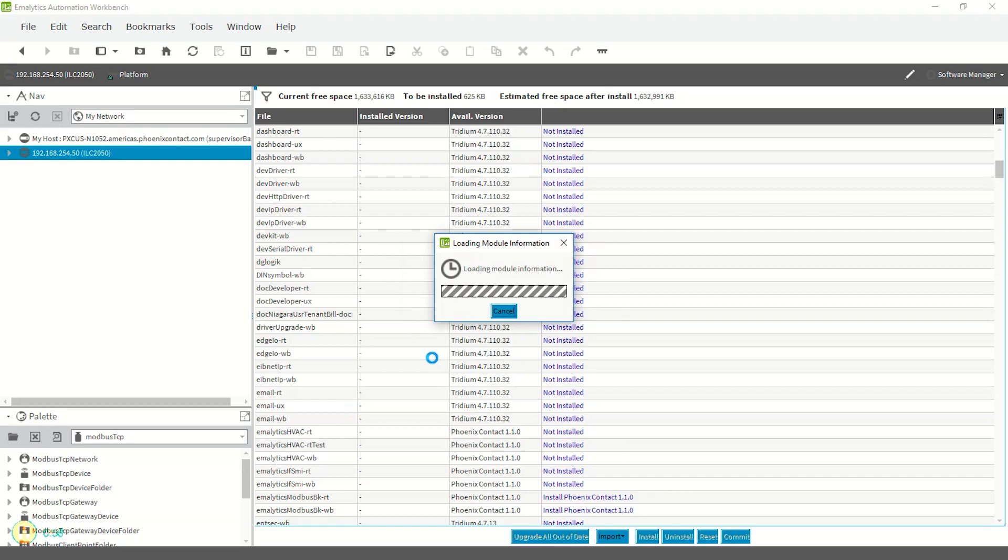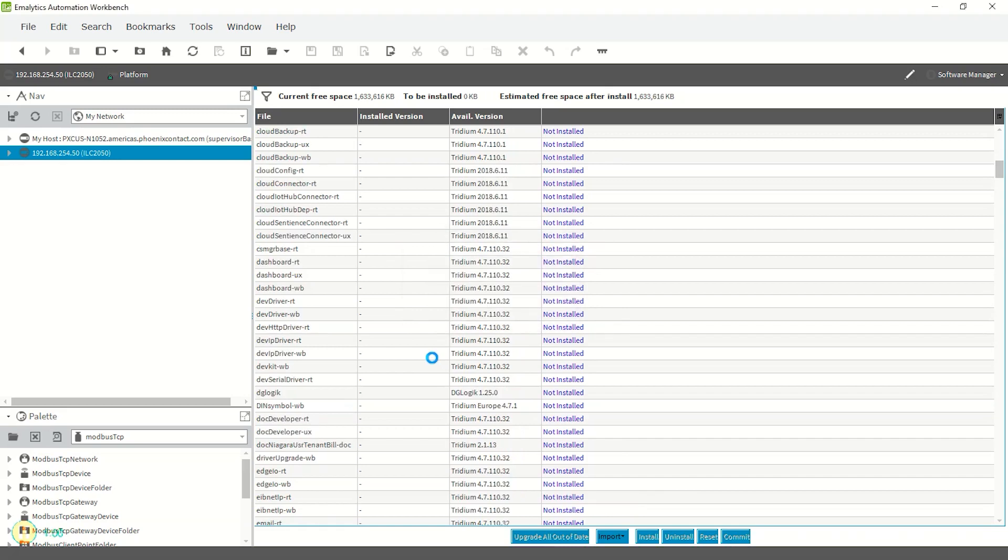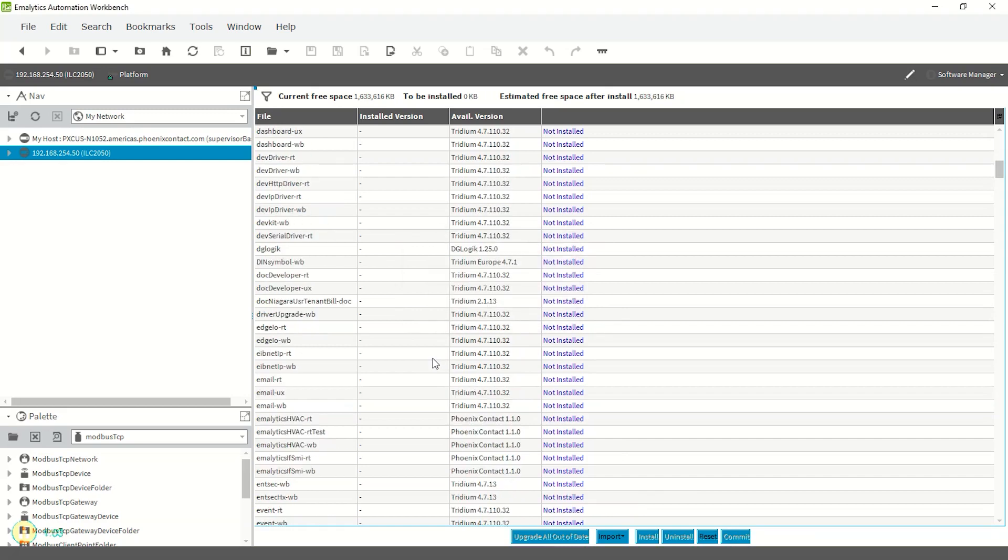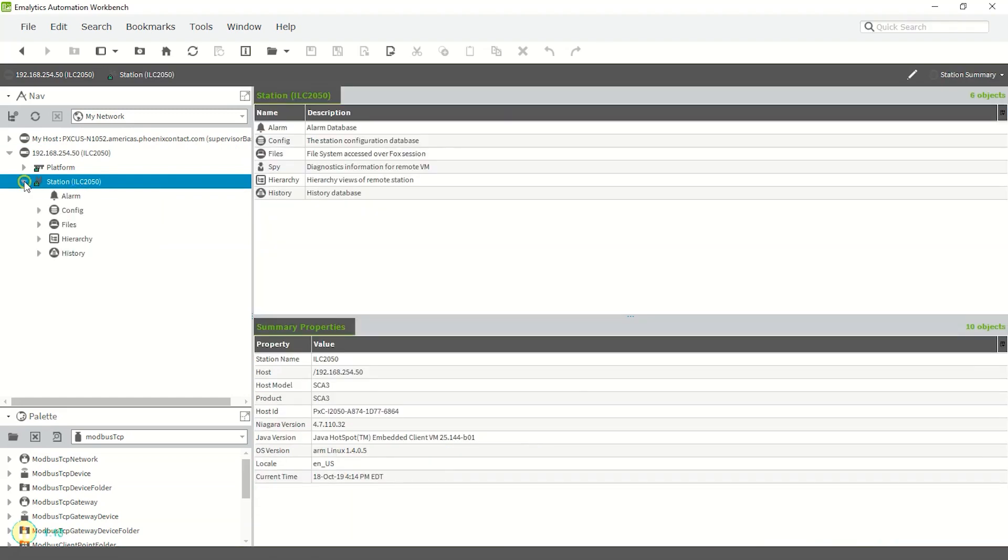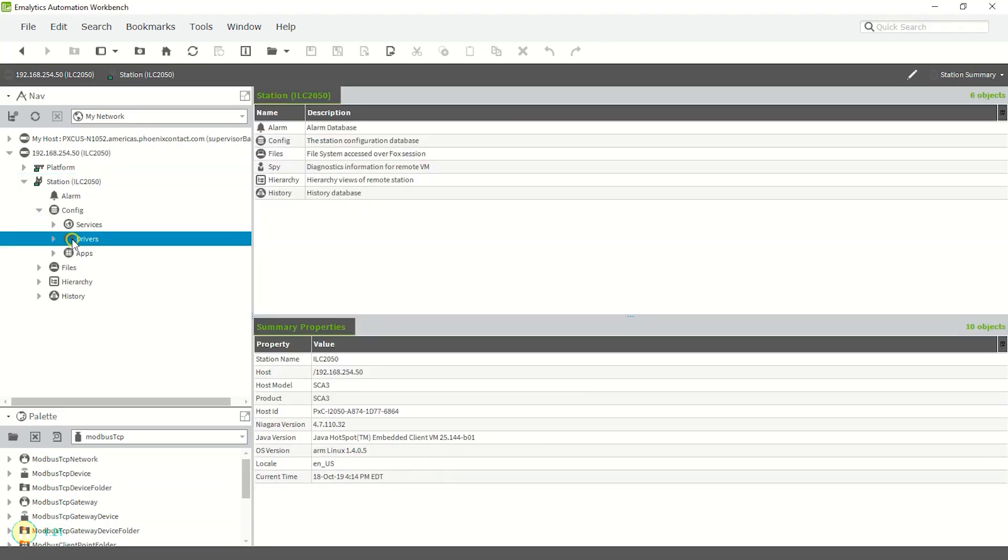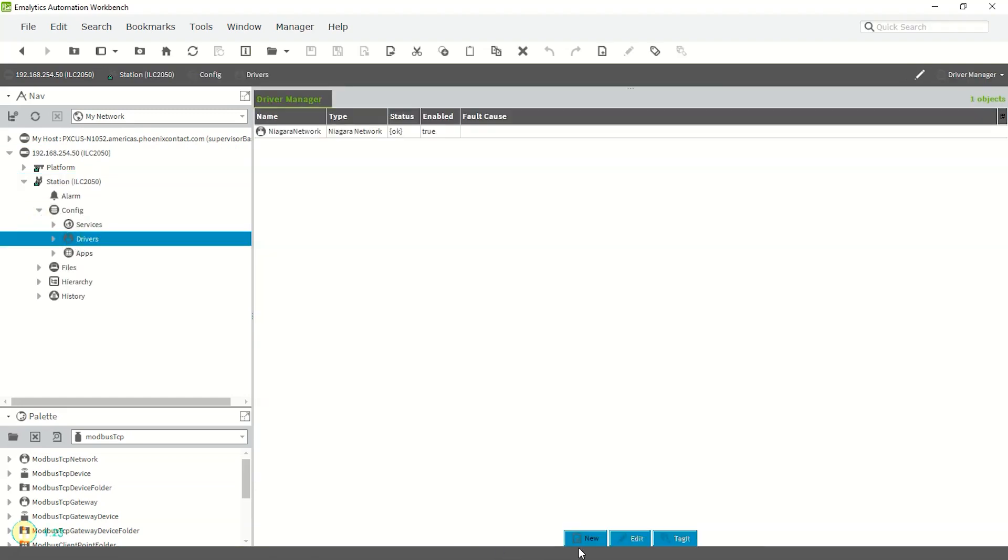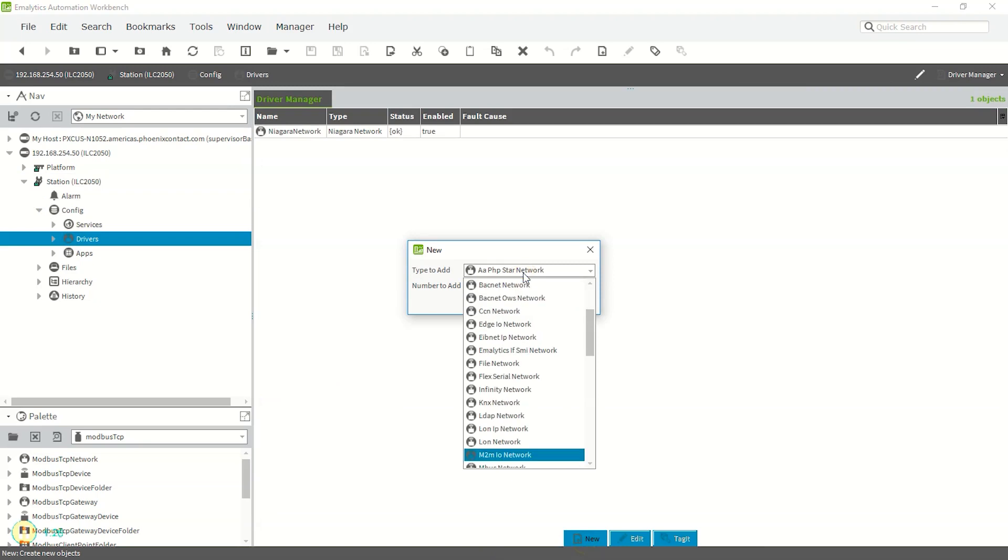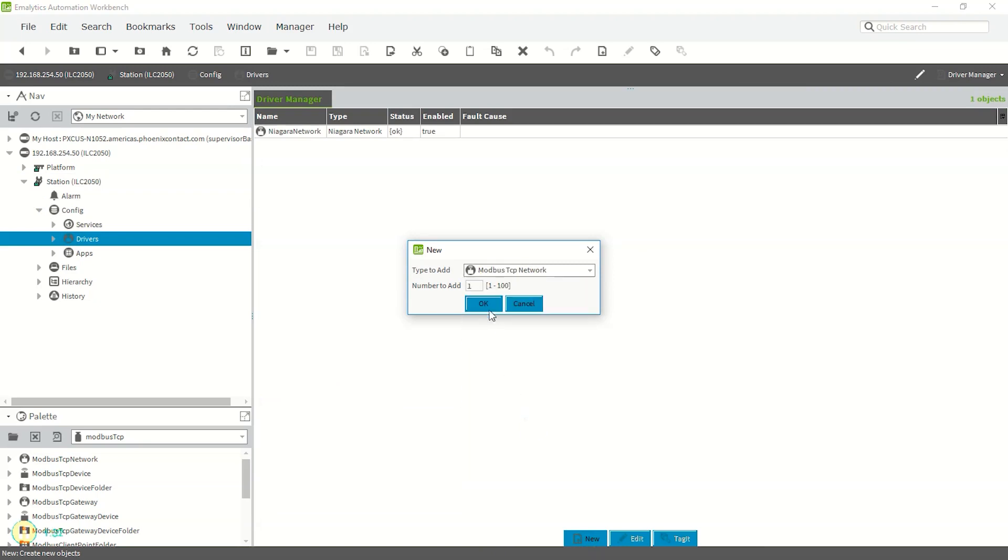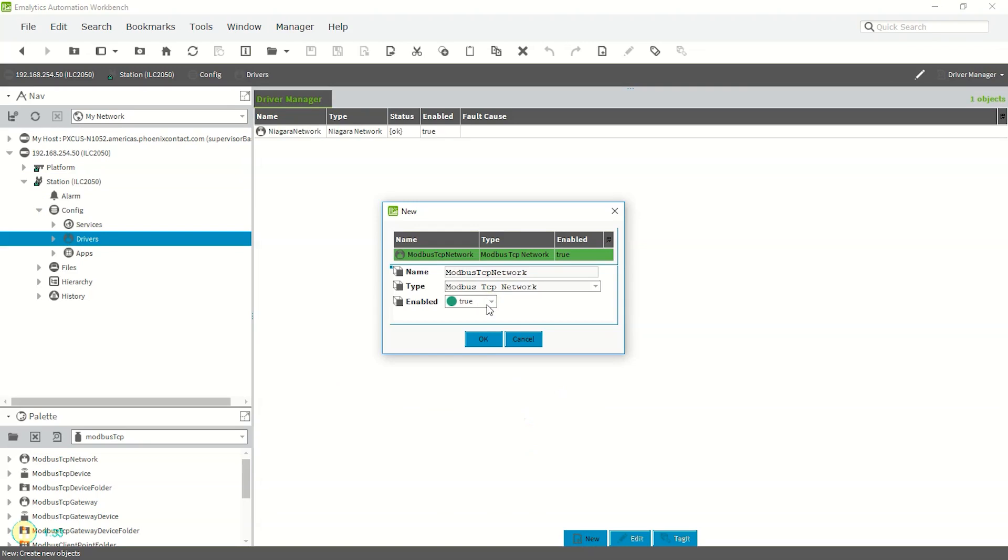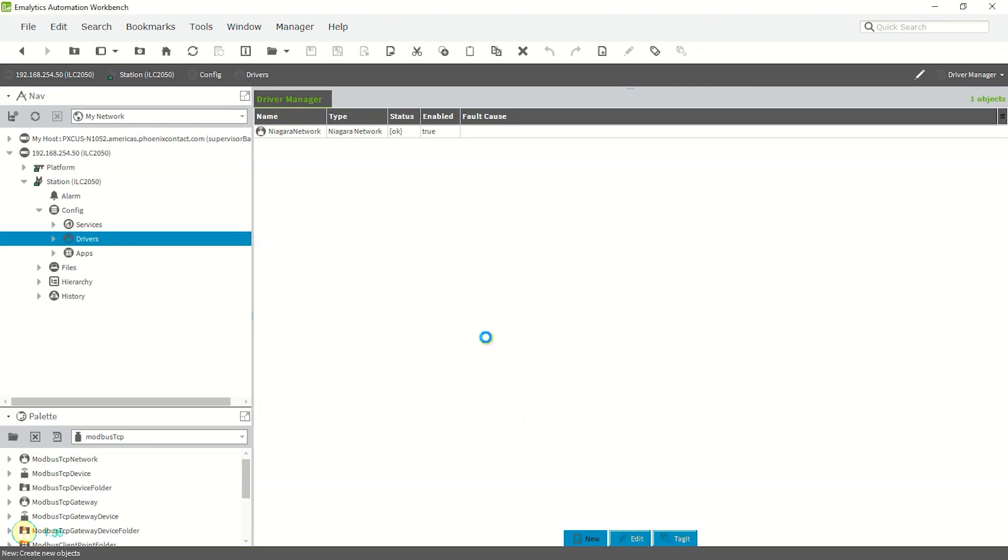Open a connection to the station of the controller connected to the Modbus I/O. Navigate to the driver's portion under Config. In the Driver Manager, click the New button at the bottom and select Modbus TCP Network from the drop-down menu. Click OK, then click OK again to confirm the new driver.